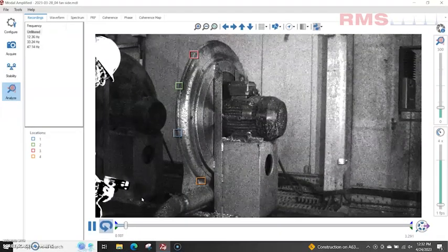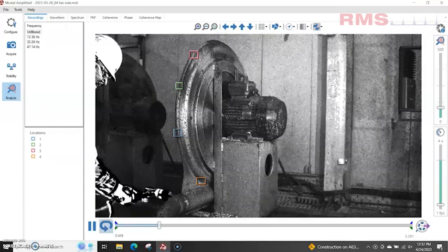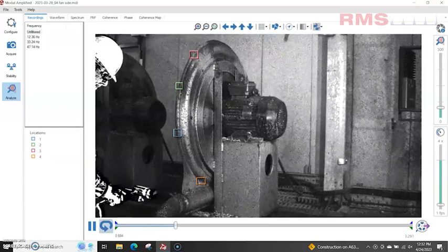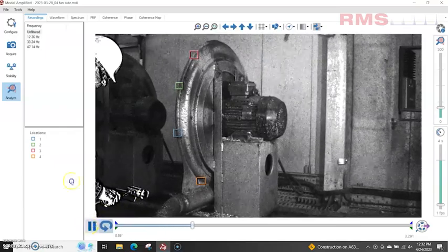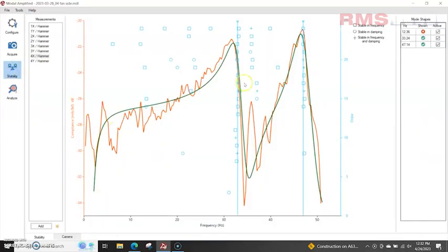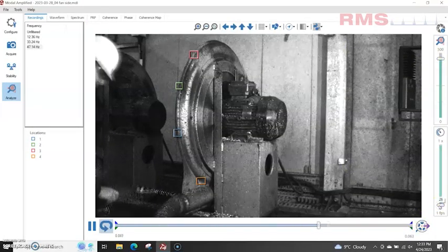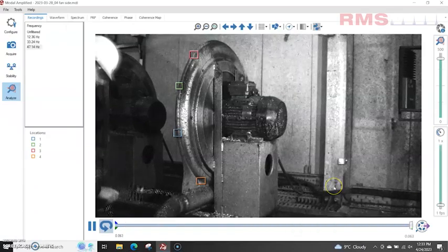And this frequency was around 47 Hertz, so I then changed some different angles, bumped it again, drew some measurement points, and got a really clear response at 47.14 Hertz, which is within 20% of the fan running speed, and you can really see the rocking motion there.